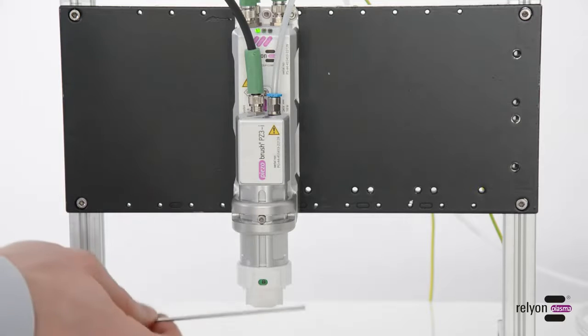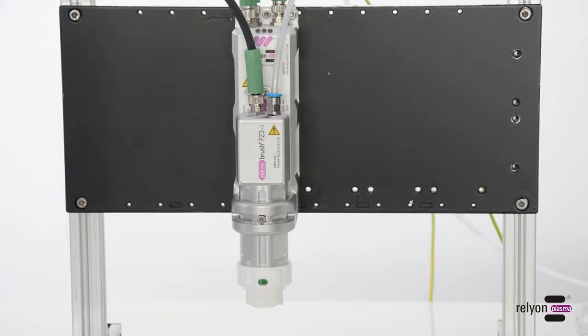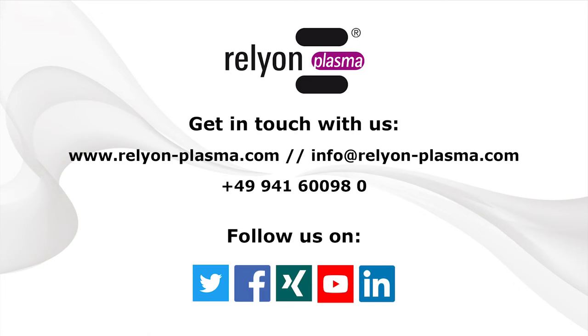If you have inserted the standard module but use an electrically conductive substrate, the device goes into fault mode. The Piezobrush PZ3i recognizes that no reliable plasma generation has taken place because you are using the wrong module. Please change to a module for electrically conductive materials. If you have any further questions about the Piezobrush PZ3i or plasma in general, please do not hesitate to contact us.